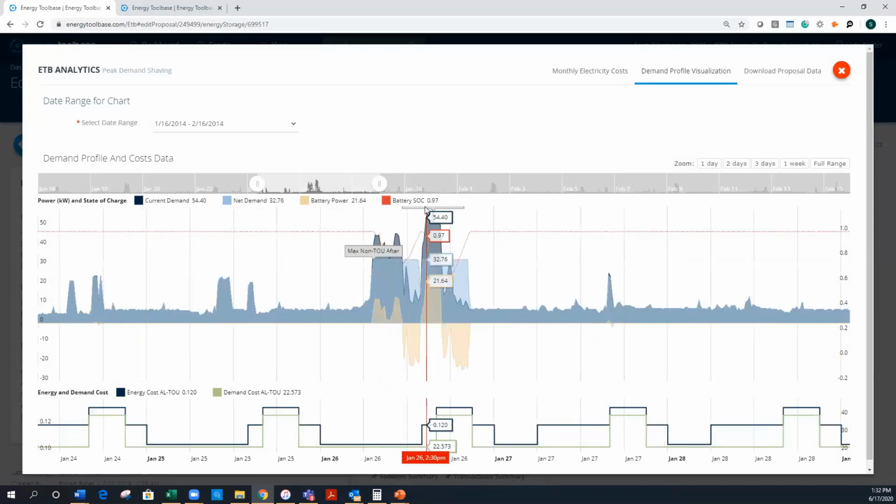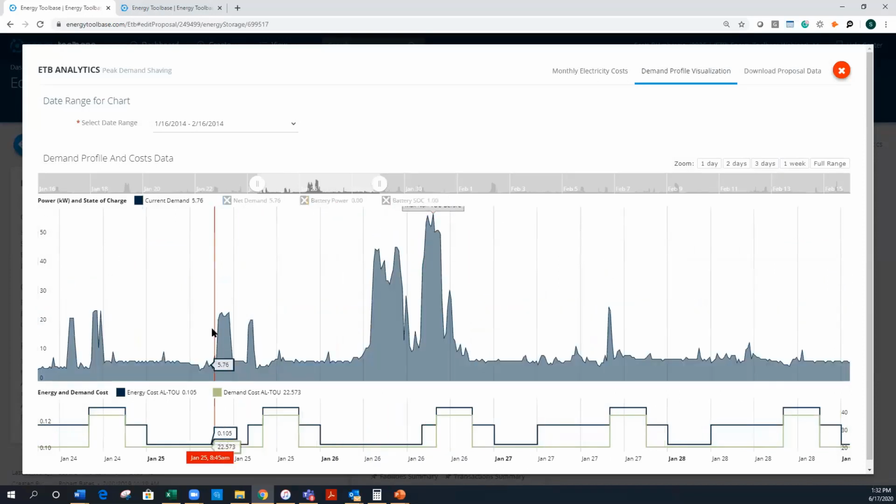Now, behind the scenes, this is really where I want to go, right? We love granularity, and this client was a church load profile, right? So you could see we're spiking, right, and cutting those peaks, peak demand shaving in here, right? And let me zoom into a day and time. Let me kind of undress this for a second here.